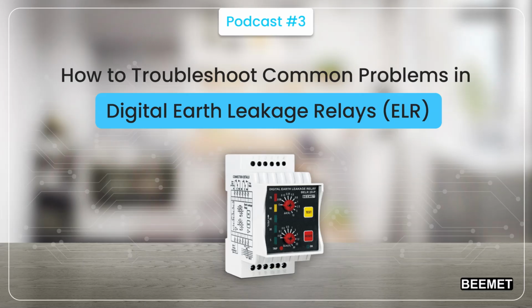Advanced diagnostic techniques for digital ELR faults. Looking more closely can be quite useful when problems aren't obvious. Checking earth resistance and waves for electricity noise is an advanced diagnostic skill for relay faults. Keeping log files can help solve difficult problems. Early warnings are also crucial to power system protection. That alerts you of a system shutdown.